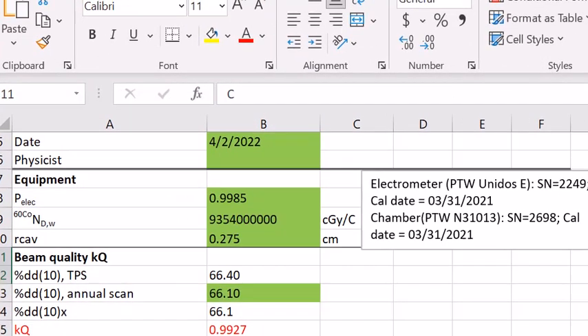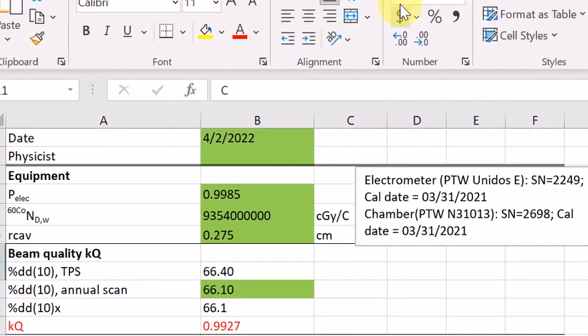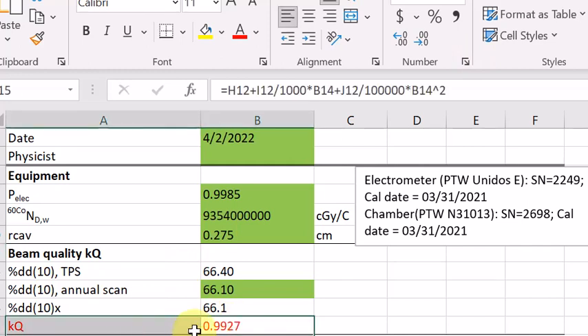In our case, the KQ value for a 6MV photon beam is 0.9927. That's the example that I want to show you for a photon calculation. I will briefly introduce how to obtain KQ factor for electron beam in the next video lecture.